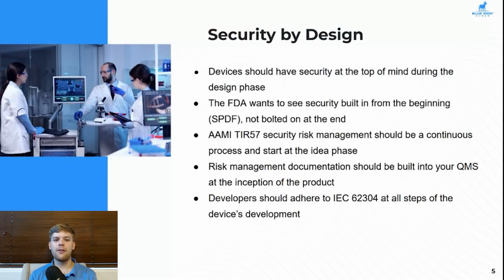Now, the core principle that the FDA really wants to enforce is security by design. So devices should be designed with security at the top of mind. It should be the first thing that manufacturers are thinking about as they make design choices. The FDA wants to see a secure product development framework and cybersecurity implemented at the beginning, not bolted on at the end. Bolting on security at the end is typically going to be more expensive, more time consuming, and ineffective. So the controls that are in place are not going to be as effective as if the device had been designed securely the first time around.